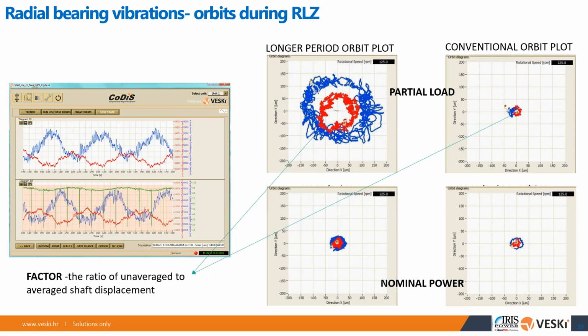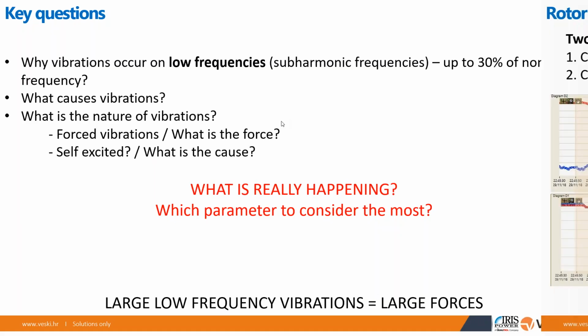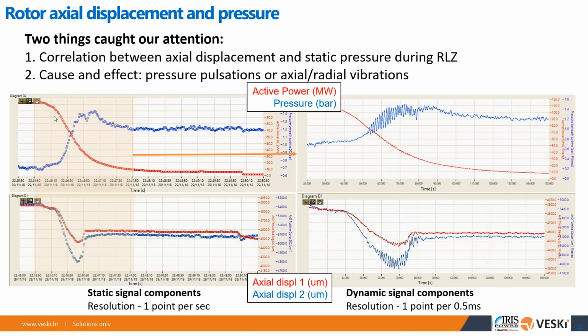So how to avoid working in the rough load zone, and how to set up protection? All right, to avoid working in the rough load zone means you just have to pass through it. There's no way you can completely avoid it, but you go through the rough load zone as fast as you can. So in this case, just run through it. It depends, a couple of minutes, how fast you can.